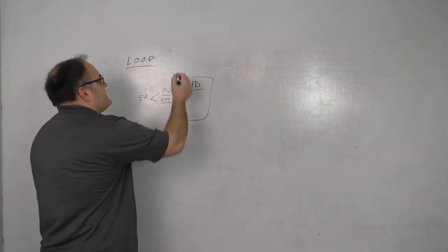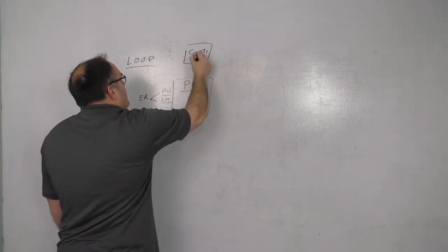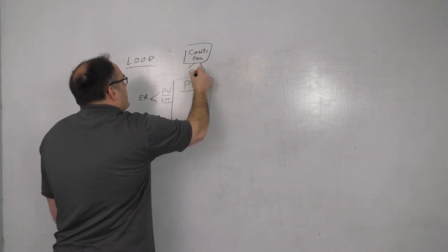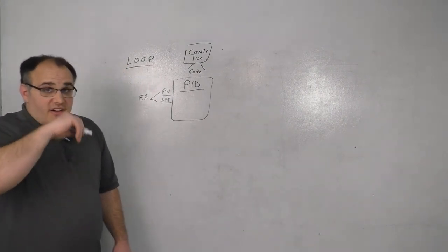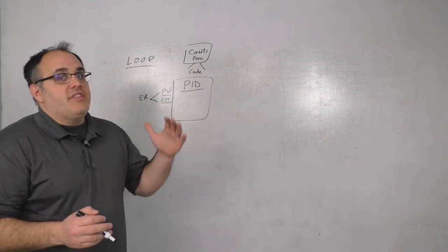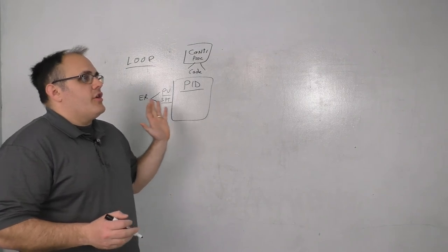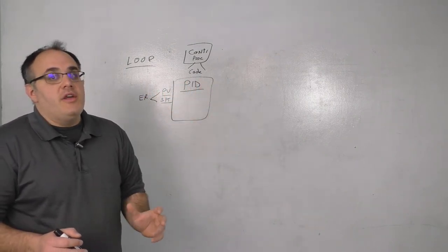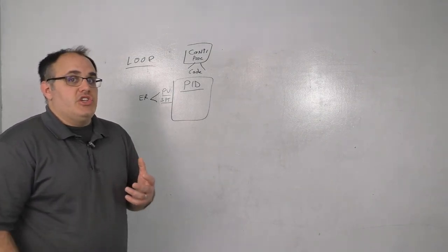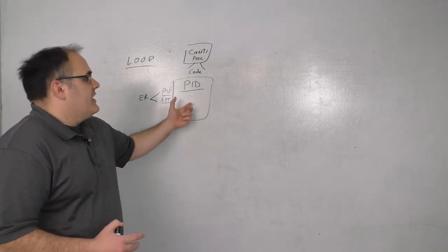Now, what happens is inside your controller, you have a processor. And your processor processes code. You know, I really liked when I started off early in my career with Alerton because you had to name or number the individual blocks 100, 200, 300 in sequence. And that is the order in which the controller would execute the code. It really helped me learn and appreciate the importance of code execution and code order and when you do certain things. And it made me really appreciate this loop.